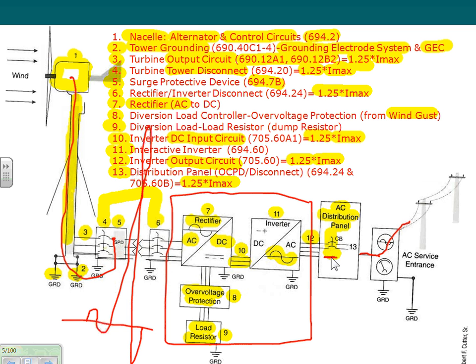So you have to have a disconnect. There are two ways of tying in. If you tie in before the meter, and before the disconnect, then you have to have a disconnect from the grid. If you tie inside the panel, then your circuit breaker will act as your disconnect from the grid. Yeah, I was just thinking, if the grid were down, could you still continue to generate power in the building? But in this instance you're not doing that, that's only in the hybrid standalone.